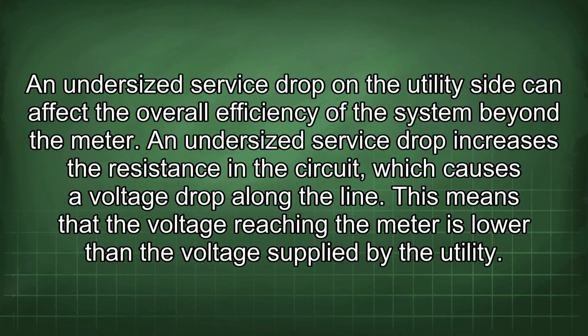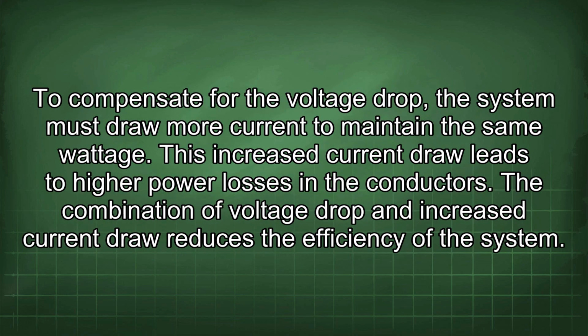An undersized service drop on the utility side can affect the overall efficiency of the system beyond the meter. An undersized service drop increases the resistance in the circuit, which causes a voltage drop along the line. This means that the voltage reaching the meter is lower than the voltage supplied by the utility. To compensate for the voltage drop, the system must draw more current to maintain the same wattage.